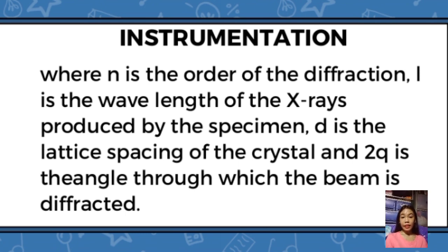And then, the crystal analyzer. The emitted X-rays are then directed towards a crystal analyzer, which can be composed of materials like lithium fluoride or quartz. The purpose of this analyzer is to separate the emitted X-rays according to their wavelengths. And then we have Bragg's law.